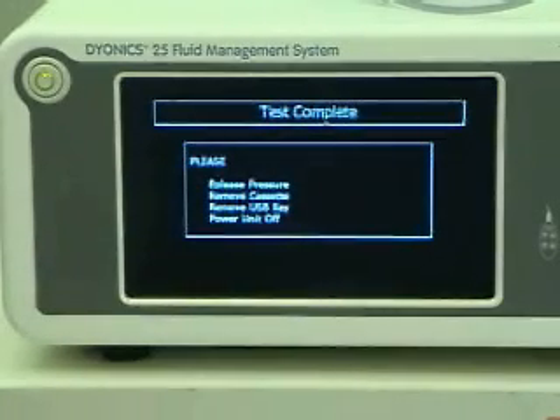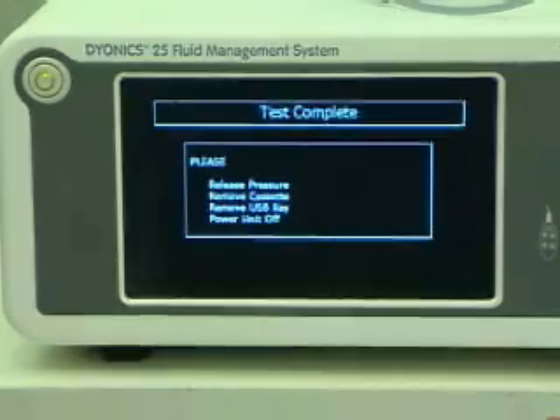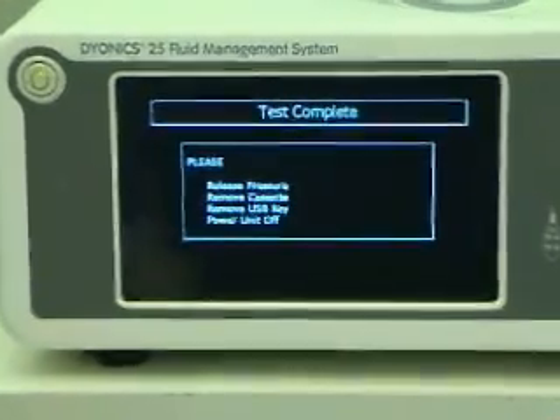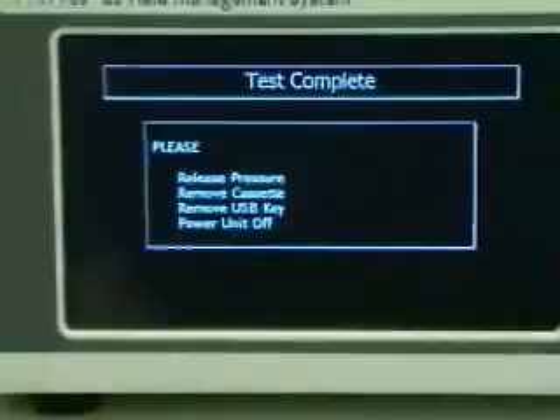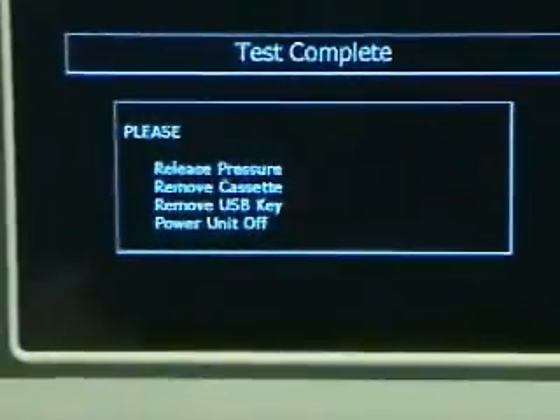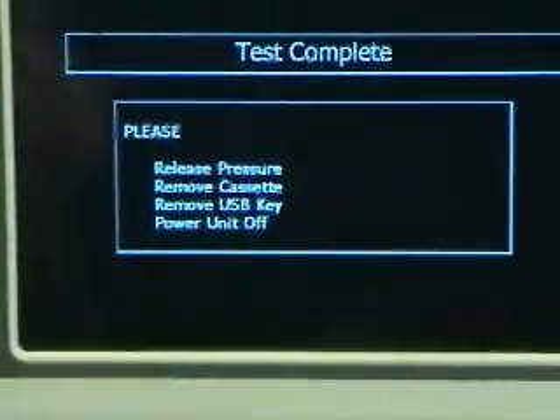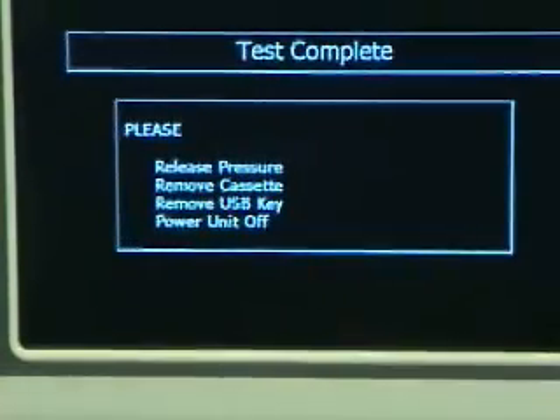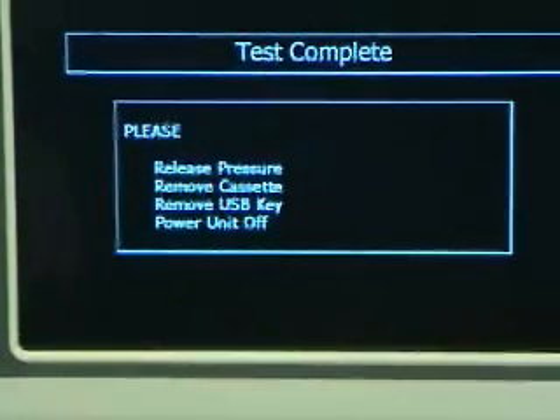You press the stop button, it tells you the test is complete. It tells you to release the pressure from the tubing, take the cassette out of the pump, remove the key and turn the pump unit off. So if you do that, remove the USB key from the back, once you turn the pump back on again it'll work normally, but what you've done is a quick check using the Biomed key to verify that the transducers are in calibration and to test the flow rate of the pump.